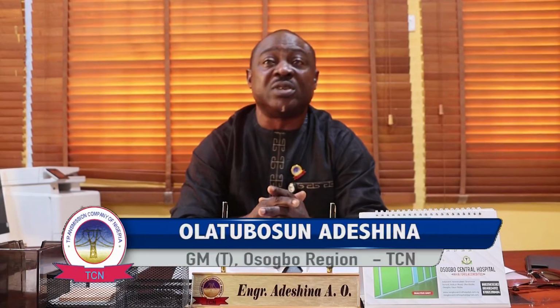Unfortunately, we've not been able to send so much power on this line because of the age and few limitations we have on that line. Presently, we are sending about 50 to 60 megawatts, which is grossly inadequate. But TCN is coming up with a very gigantic project at Akure, which is the commissioning of a 330/132 substation. In this station, we are going to have 2x150 MVA 330/132 transformers, which translates to 300 MVA. And then on the 132/33 side, there is the installation of 2x60 MVA ongoing, which translates to 120 MVA. On completion, it will greatly improve supply to both Ondo and Ekiti states.